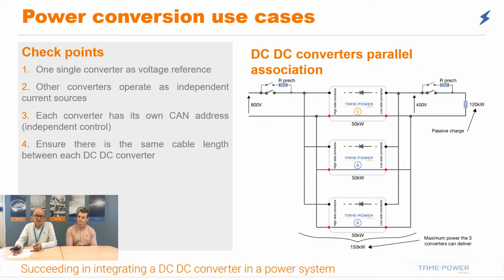If you want to change the output power, you would have to pilot through the CAN bus the converter number 2 and 3 with other values of current, just to decrease the output power. The very last one to modify should be the first unit, which is determining the voltage. In fact, this one shall always determine the voltage, so it should be the last one to be modified when you want to change the output power.